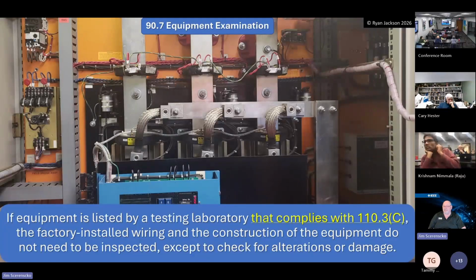Also, 90.7, make sure that the equipment listed and tested that complies with 110.3(C), that the factory installed wiring and the construction of the equipment do not need to be inspected except to check for alterations or damage. We do have some inspectors over time that go out there and start, you know, I don't think that ground strap is big enough. I'm like, you don't get to make that decision, okay?